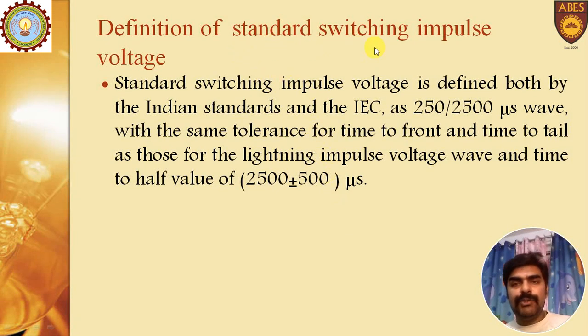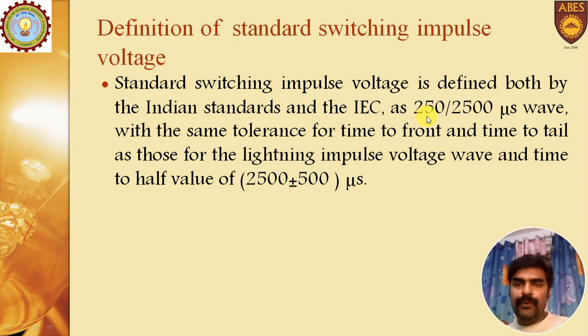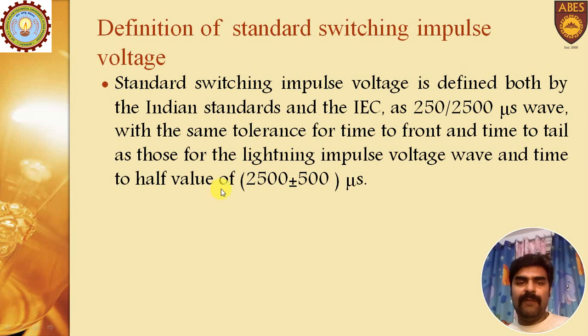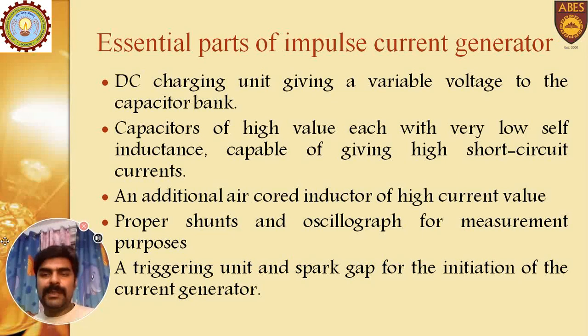The next question is the definition of standard switching impulse voltage. As per Indian Standard and IEC standard, it is defined as a 250/2500 microsecond wave, with the same tolerance for time to front and time to tail as for lightning impulse voltage. The time to half value is 2500 plus or minus 500 microseconds.